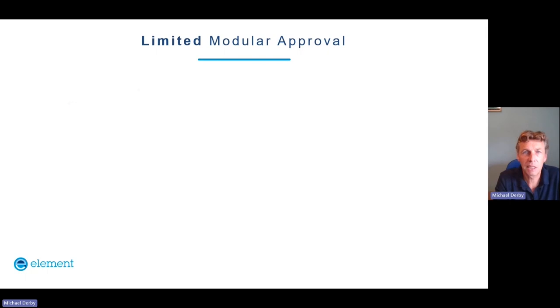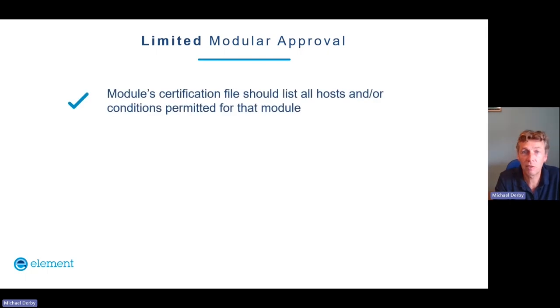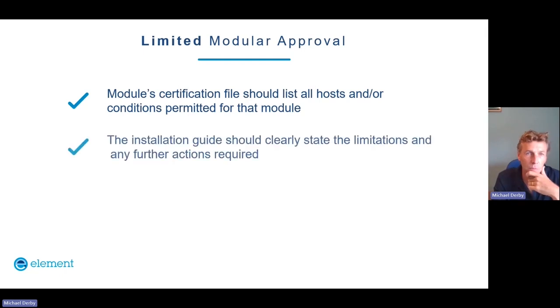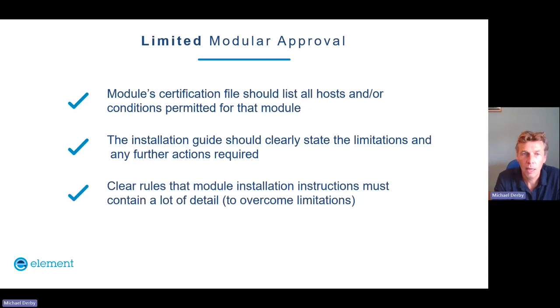So with regard to limited module approval, then, the module certification file must list the host or series of hosts and the conditions for that module, and how the module manufacturer ensures that it will remain compliant in every host. The installation guide needs to be really clear on how they guarantee it, but it's not just a case of giving some instructions to the installer, because the module manufacturer remains responsible. So it's pretty clear that the module installation instructions must contain a lot of detail.